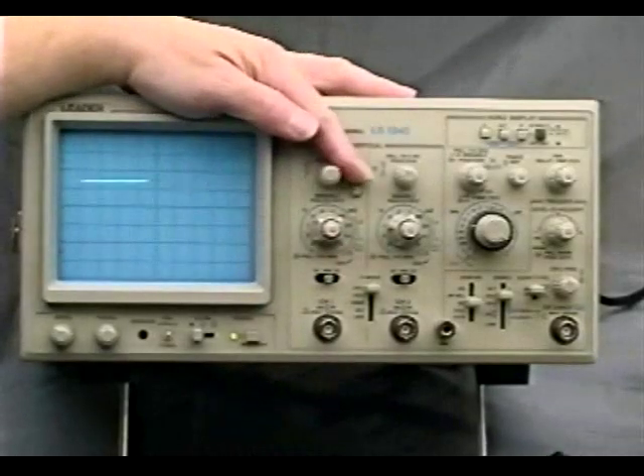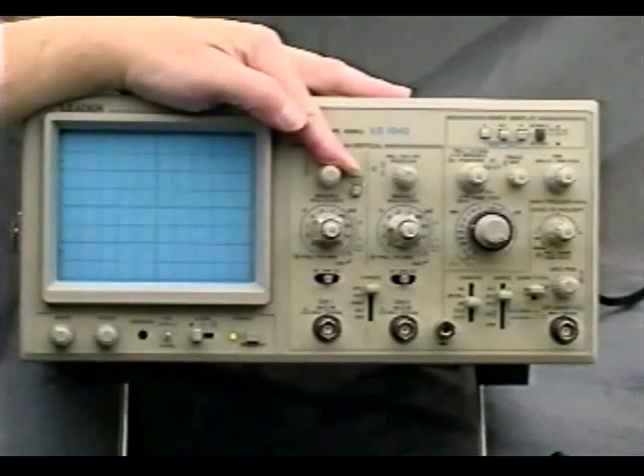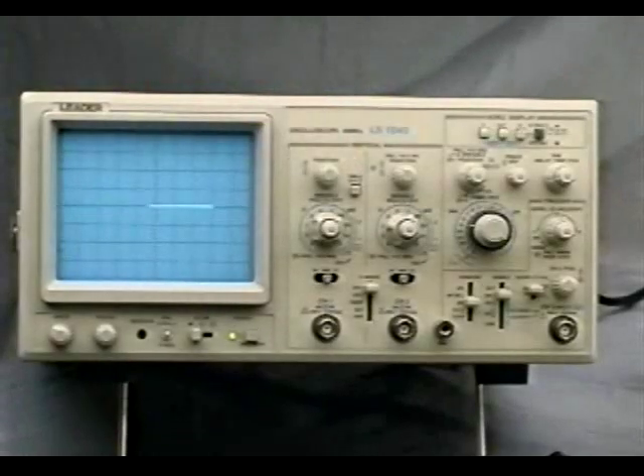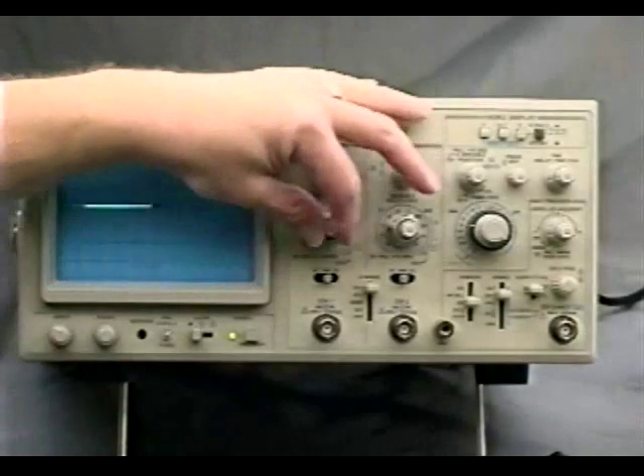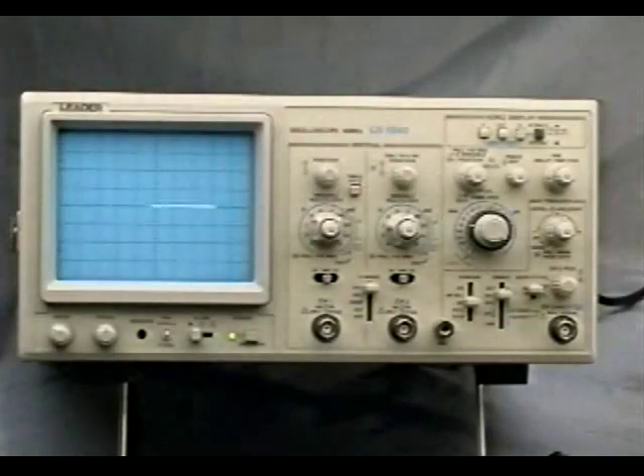Rotating the vertical position control allows me to place the ground reference trace at any point on the screen. Here we've positioned it at the exact center of the screen. Don't forget to verify that the vertical attenuator variable Vernier control is in the calibrate position. Otherwise, you'll affect measurement accuracy.